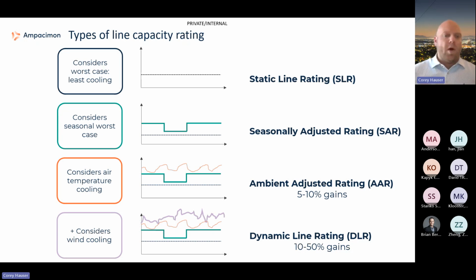And one other note before we move on: these estimated gains are extremely dependent on the static and seasonal ratings and the assumptions that are used. So if you're using very aggressive assumptions, or a fixed wind speed that is extremely high, higher than the 2 feet per second that's recommended, that's where you may not see as many of those gains, because you're already capitalizing on some, but likely without great visibility. So dynamic line rating really allows you to have that full scope into the values and the comfort value that goes along with it.